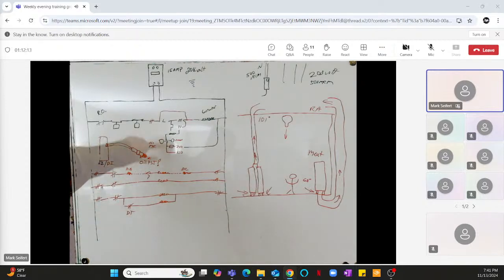The same way this differential switch allows electricity to flow, if the oil pressure goes up, it opens up. It doesn't allow electricity to flow anymore. There's no oil pressure, it's down, allows electricity to flow, opens that up. This is the same thing, except all it is, the DI is checking for resistance across there. It's an open circuit, and then it gets oil pressure, and if I'm not mistaken, it closes. But it'll work on either one. It doesn't matter. You just have to tell the controller, does it close with oil pressure or open with oil pressure? It makes no difference. The controller will do its thing. So it's all software. All this stuff is based in software.